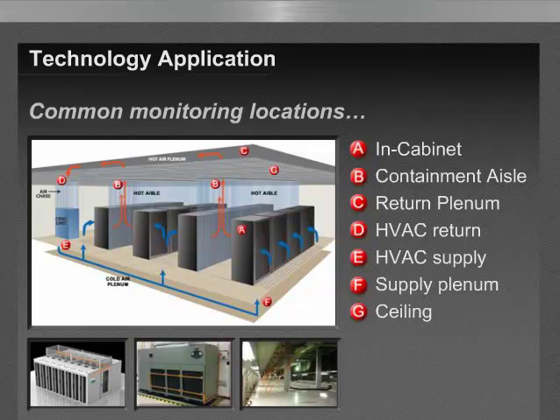Now, if you passed the air plenum and you went to the return point of the HVAC unit and decided that that's where you want to put your detection, that being point C, the return plenum, point D, the HVAC return, and if all you did is that, you wouldn't have clarity in terms of knowing which containment aisle. You'd know that there was an event. It may be further along the smoke growth chart, but you are potentially going to detect it with a very early warning fire detection system.